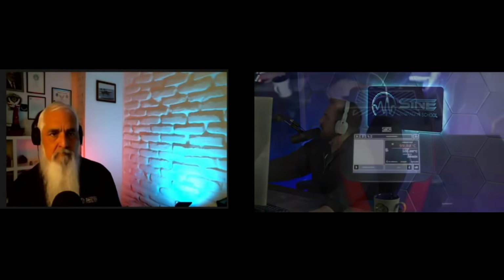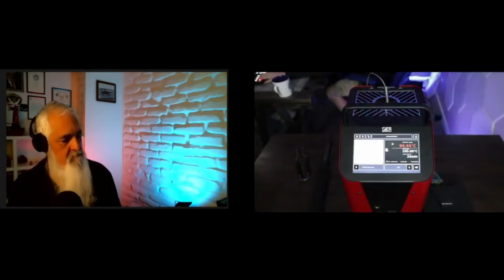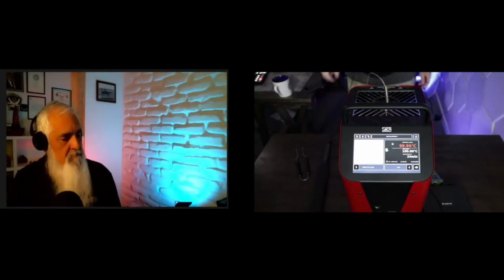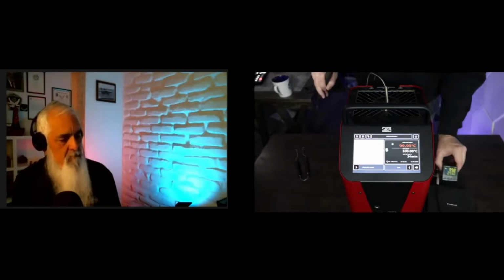So hold on, let's look at our sensors now. Let me go walk over there. All right, so where are we sitting? Now we're at 99.9 and 99.9. So most likely this is an ungrounded probe, because of how long it took to stabilize. If it was one that was grounded, where it's touching the sheathing, most likely it would have been very fast.